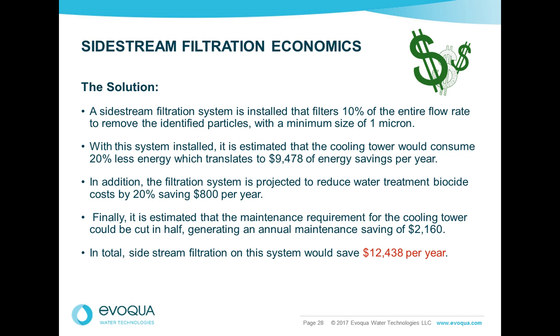So what do we do? In this case, a filter is installed that filters 10% of the recirc rate. And remember, 1,200 gallons a minute is the recirc rate, and we're taking 10%, so it's a 120 gallon a minute filter. And that filter design that was chosen is going to remove that particulate down to the 1 micron. Again, the particle size analysis showed that's necessary. And after installing the filter, the particulate forming that 0.02 of an inch of deposit are gone, usually over a little bit of time. So this system gains back that 20% in energy it lost when the deposit was there. So that's about $9,500 in savings annually.